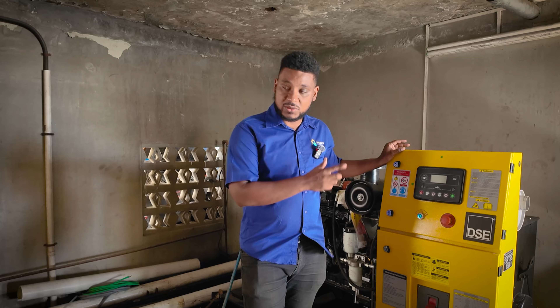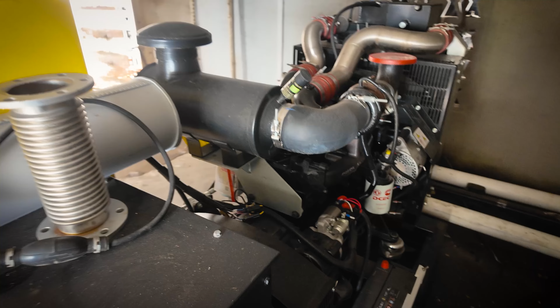We've rolled the generator into place, run the cable between the generator and the automatic transfer switch, and set up the electrical infrastructure in terms of breakers. What's left is to switch the main power to pass through our changeover switch, so that it can select whether to take power from JPS or the generator.